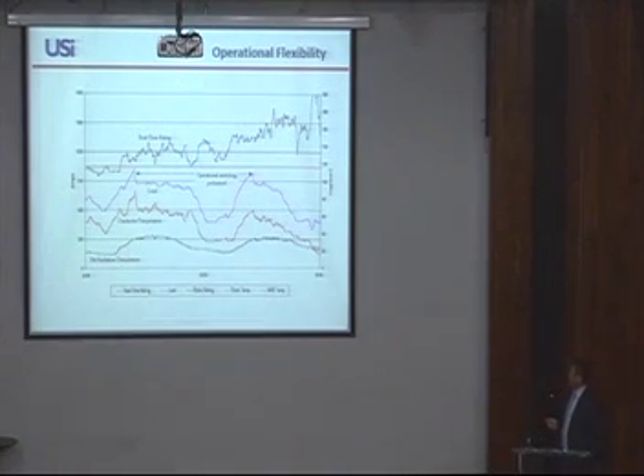There's another case where the dynamic rating was installed but not used. It was in a test phase, and what happened here is there's some conductor temperature. You see the red line here. This was the conductor temperature without current. This is with current. This is a load here, and this is a DLR and the static rating. So you see here, there was a peak.